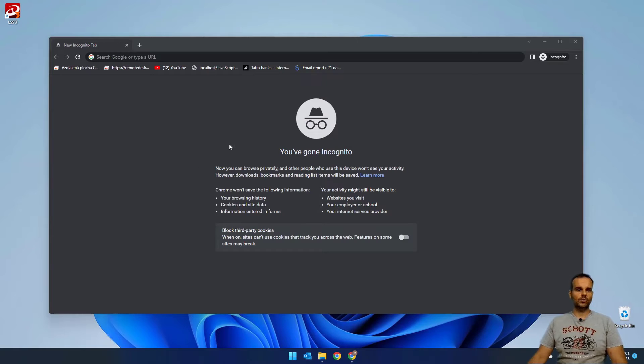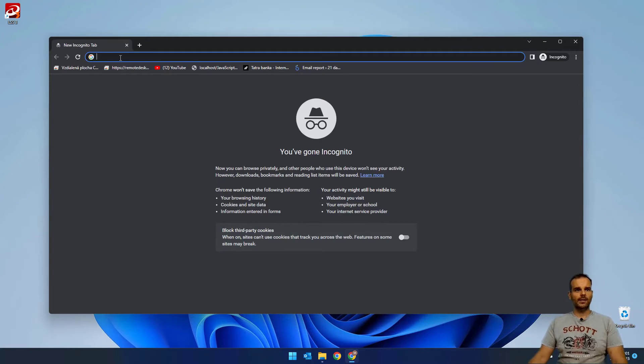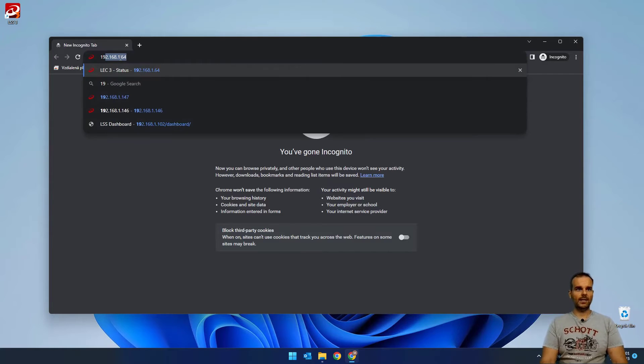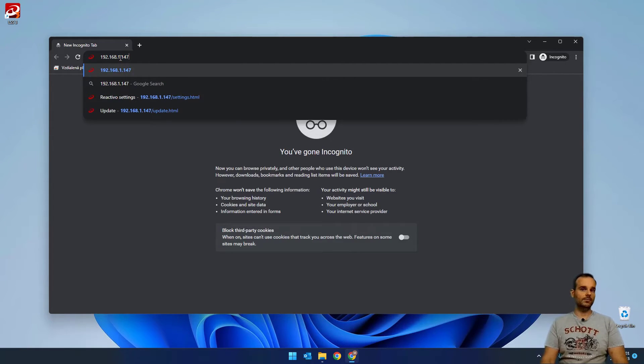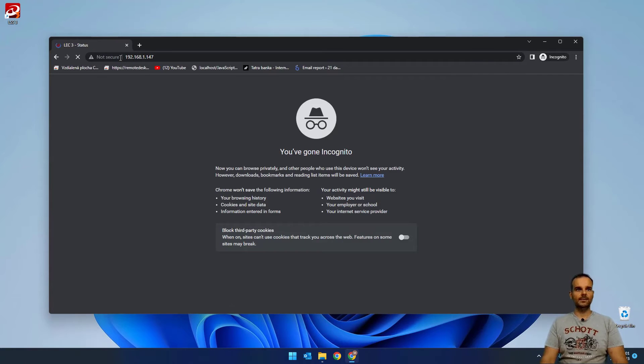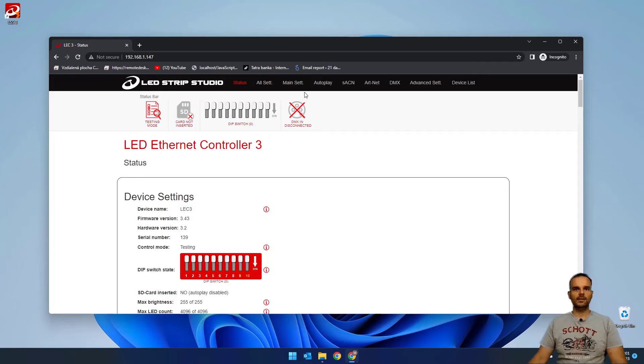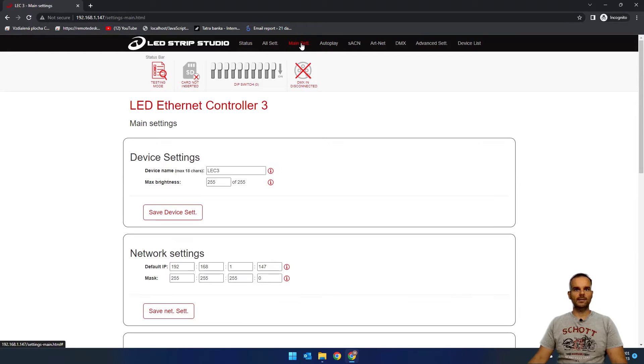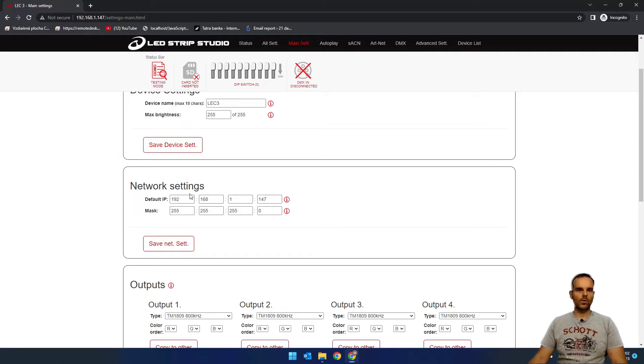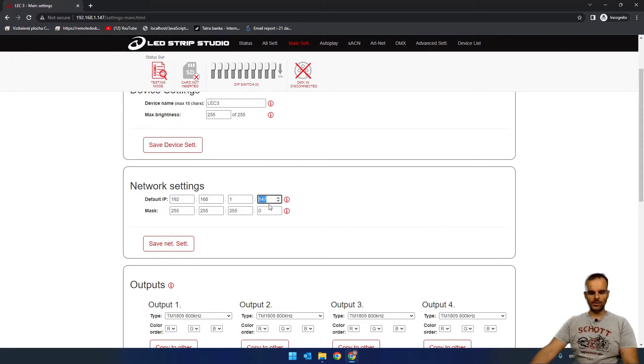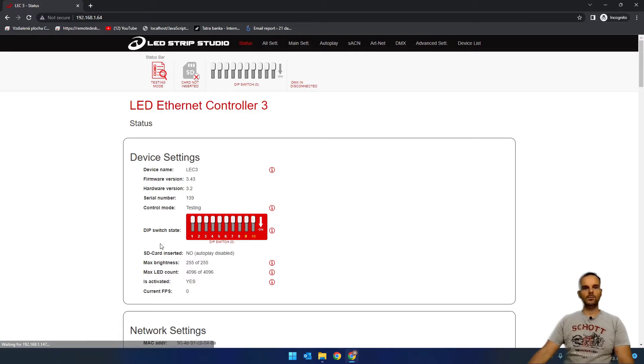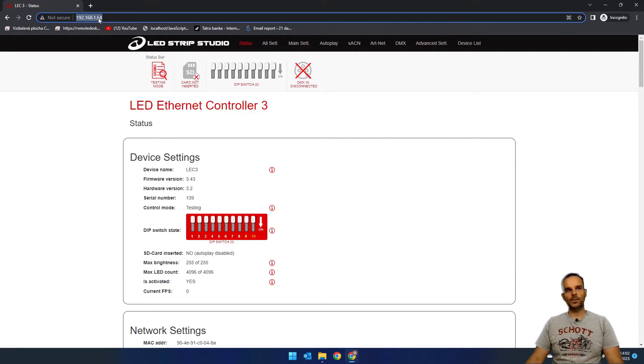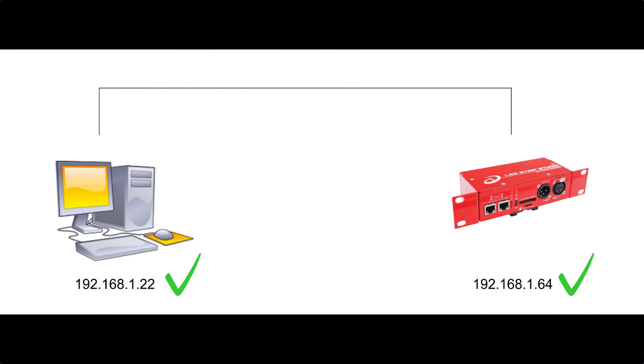To get to the settings of the device, you have to use the web browser. Here in the address bar, you type in the IP address of the device. In my case, 192.168.1.147, which is the default address of a new LEC3. As you can see, I have the device settings in the web configuration. If you want to change the IP address, go to 'Main Settings' and you can change the whole IP address there — for example, change it to .64. Don't forget to save the settings using the save button. Now the device IP address is changed, and I'm already on the new IP address. It's quite easy.